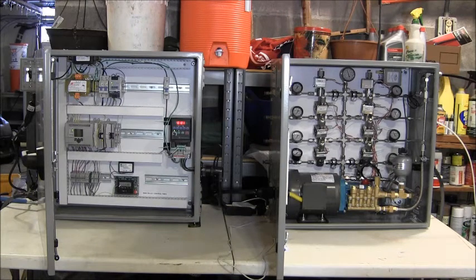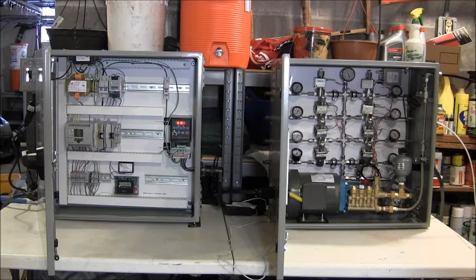There is a disconnect way over on the left here. There it is. I think you can see it's just a standard disconnect. It does have a lockout assembly in it, but it's just a single-phase breaker or disconnect switch that supplies power to this assembly. So even though there's just 115 volts coming into it, the variable frequency drive, the VFD, is taking 120 volts coming in through this breaker right here and actually converting it to 208 volt 3-phase going out. And you can see that there's 3 wires down here going out to the 3-phase motor.